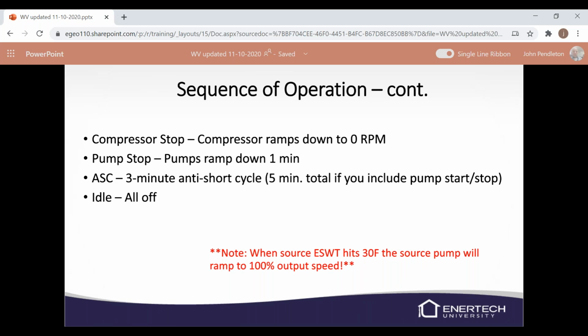On a compressor stop or an end of a call, the compressor is going to ramp down to 0, and then the pumps are going to ramp down about a minute after that compressor is stopped. It will then show on the screen ASC, and that's a 3-minute anti-short cycle timer. After that 3 minutes, if there's no call, it'll just say idle on the main screen.